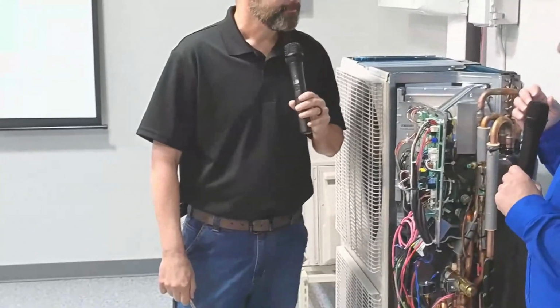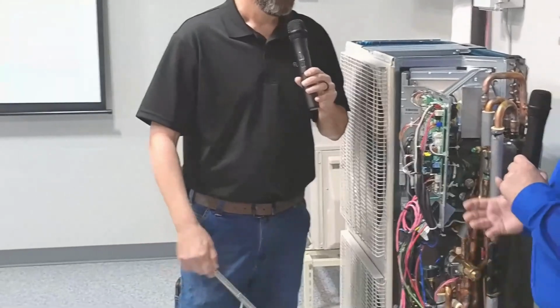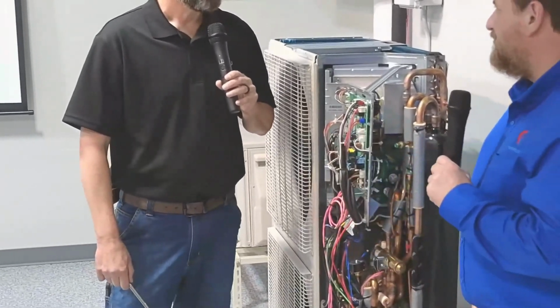So in any refrigerant system, any mini split, any heat pump system, you're going to have your compressor down here, and it's part of the vapor compression cycle. We're going to have a low pressure vapor, it's going to compress it and give a high temperature, high pressure vapor. In the class, we stressed so much about the installation, to make sure that we had the proper amount of vapor coming back in and that it doesn't overheat. Just like with a standard air conditioner, you have to have oil return, you have to have the proper amount of superheat coming back to it, so we don't burn that thing out. So it's very similar to a traditional system.